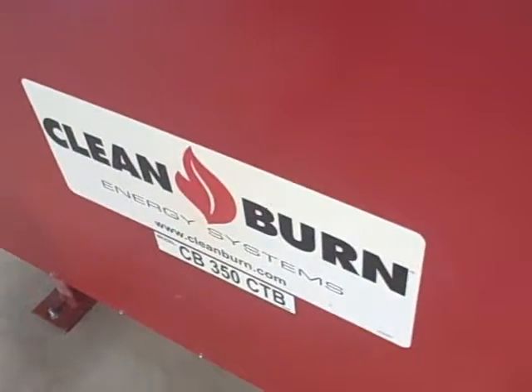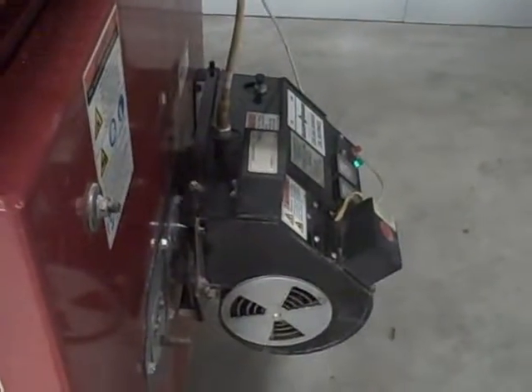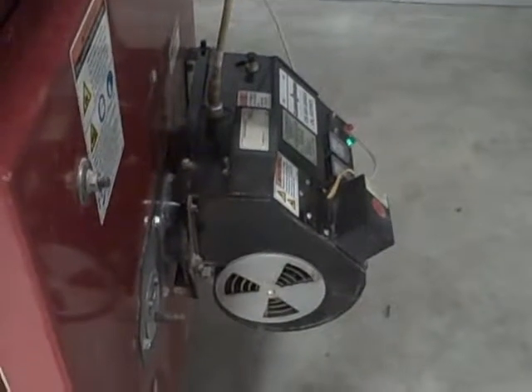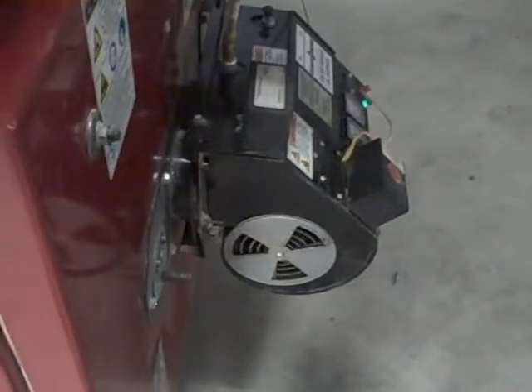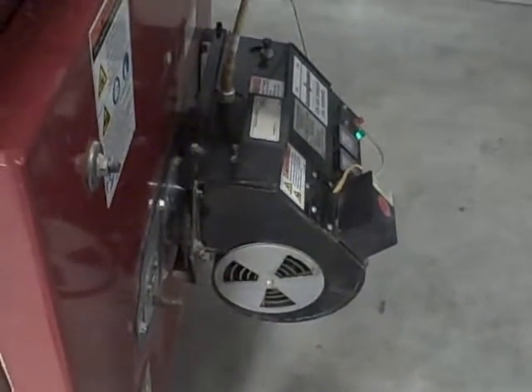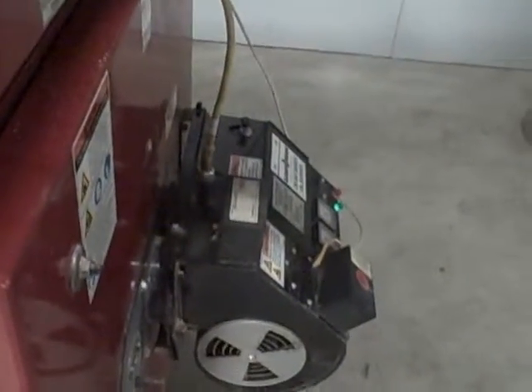I'm running right at 1,000 hours, 1,100 hours each on them per year. So I'm running someplace around 22 to 2,400 hours combined. They burn 2.5 gallons an hour. Last year I used about 5,300 gallons of waste oil, and we're heating 22,000 square feet with this system.